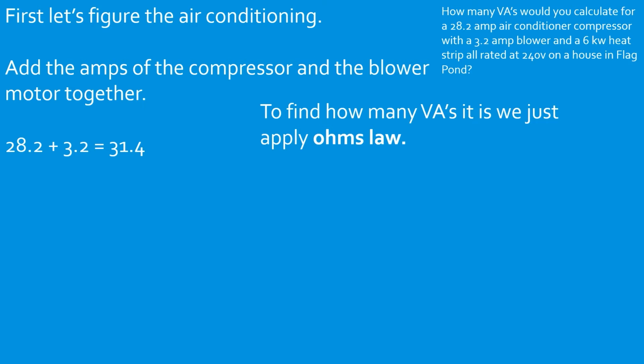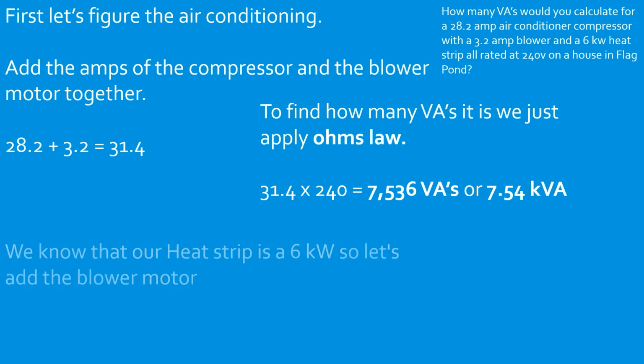Now we just need to use Ohm's law to find out how many VAs. So we take our 31.4 and multiply it by 240 volts. That's going to give us 7,536 VAs or 7.54 kVA. Now we set that to the side.